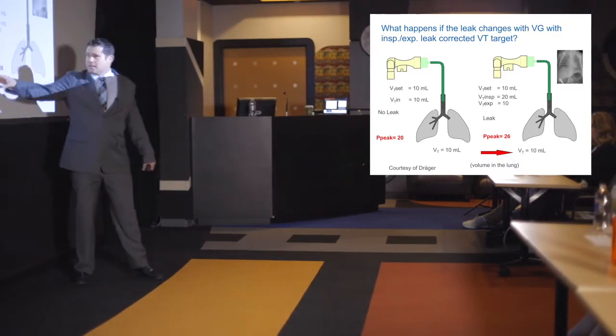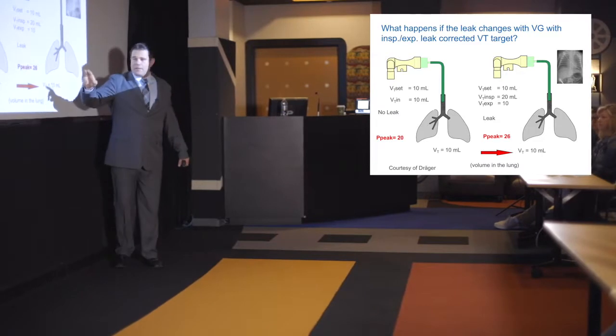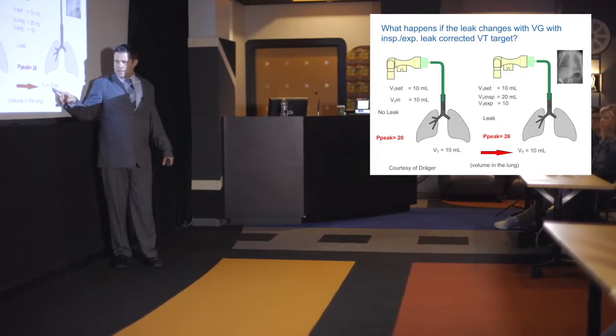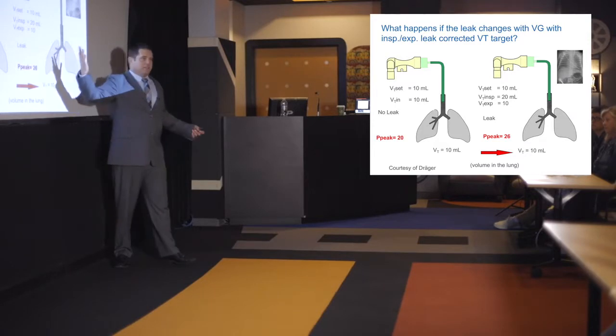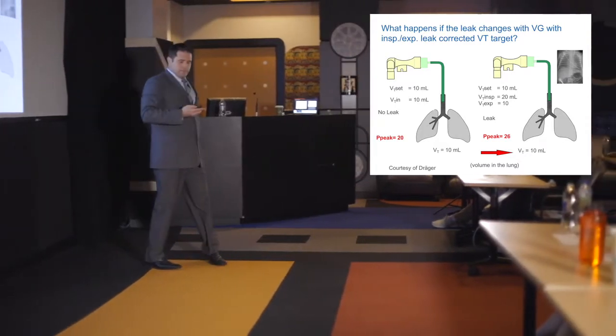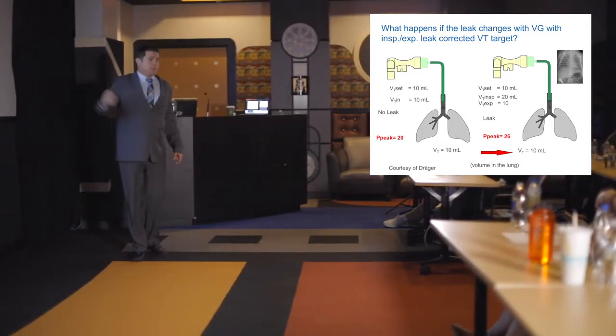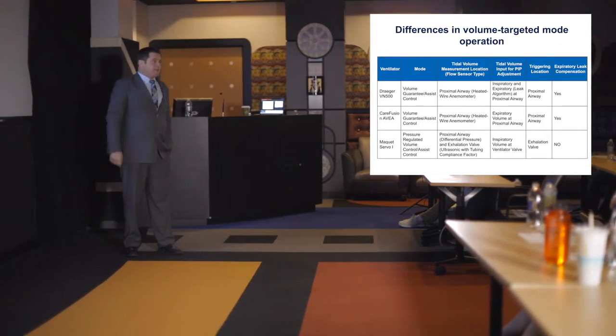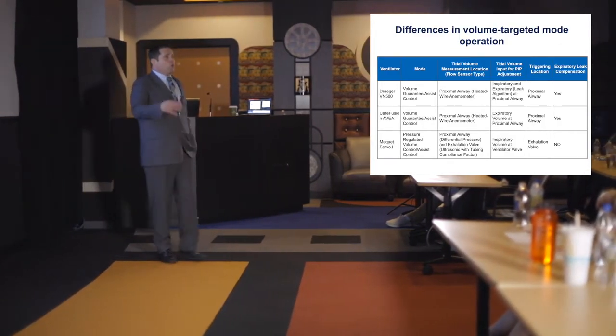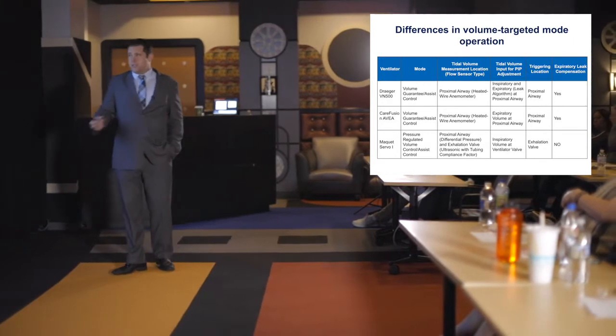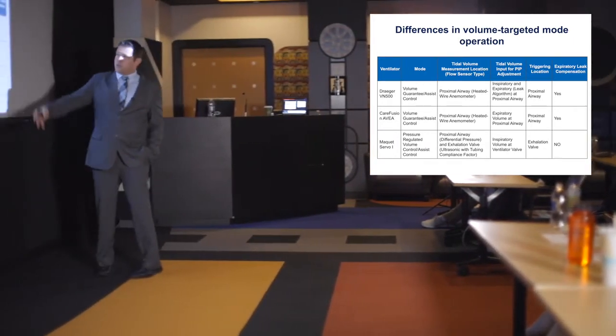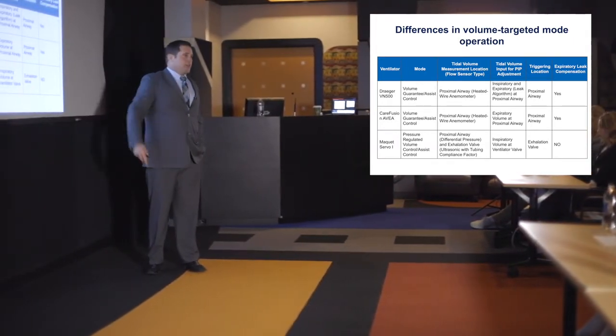So what that means is if you develop a leak, instead of having the tidal volume go down to 7 mLs, it's going to stay at 10, right? But it has to use a higher pressure. It's just physics. So then the lung looks like it's open a little bit more. So that's one of the benefits of volume-targeted ventilation, but only if you can leak correct and you can leak compensate.